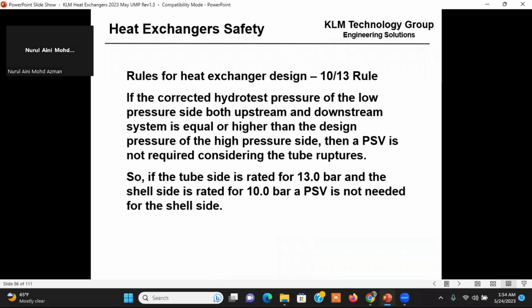So there's what's called a 10/13 rule, which I really wish it was part of the code. It's not. It's just a rule. And the 10/13 rule says that if the tube's for 13 bar, the shell side should be rated for at least 10 bar. That's the 10/13 rule. If we don't rate it for at least 10 bar, you have to add a relief valve. And the code says if you don't rate it, you have to add a relief valve. Okay. The cost of rating it for 10 bar is very cheap. The cost of adding a relief valve and the piping is expensive.